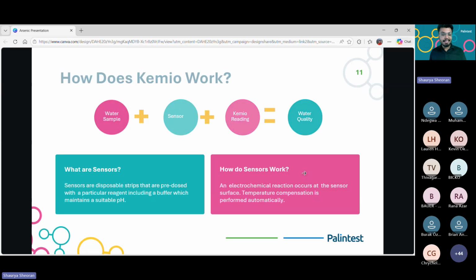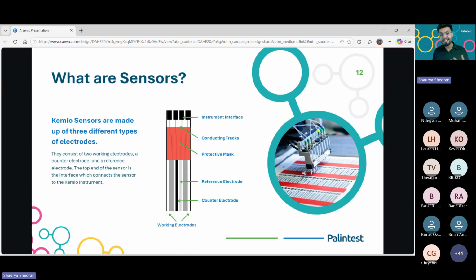So what exactly are sensors doing? Sensors are the consumable in this case. The sensor is where the reaction happens. It has multiple electrodes where the arsenic does a chemical reaction, and that chemical reaction generates a signal. So if there is a higher amount of arsenic in it, there's a higher current, and that current is then measured by Kemio and reported as a reading.